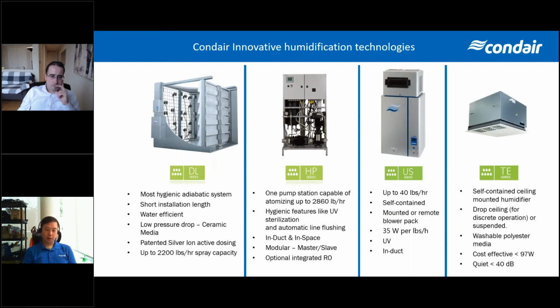And then as Nuno mentioned, primarily we focus today on our direct evaporative systems because those are really what we're seeing being used in these large facilities. But we do also have a full range of cold water adiabatic technologies. As Nuno mentioned, we have the DL, which is a low pressure atomizing system with a ceramic media downstream. We have your more traditional high pressure atomizing systems.